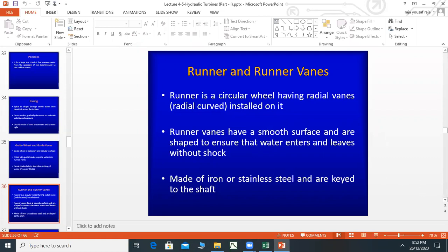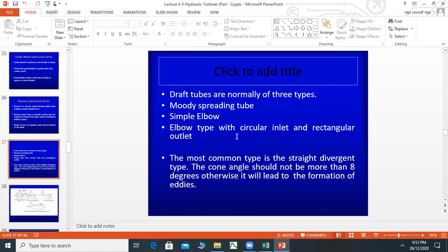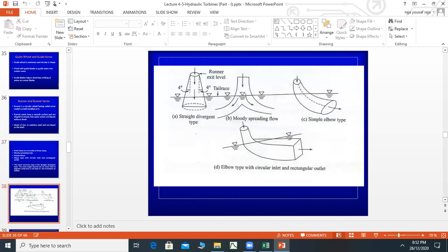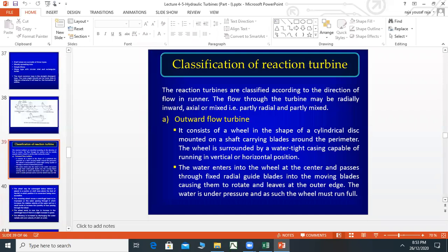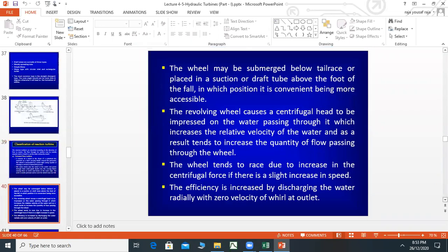Then we have draft tubes. We have three types: moody spreading tube, simple elbow, and elbow type with a circular inlet and a rectangular outlet. The most common type is a straight divergent type. The cone angle should not be more than eight degrees, otherwise it will lead to the formation of eddies.